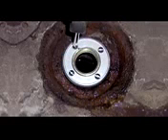Another option is to install a standpipe in the floor drain. A standpipe is an open-ended pipe that can be screwed into the basement floor drain to permit the flow of water back up as high as necessary, thereby delaying or preventing a basement flood from a backed-up sewer. Standpipes are typically 2.5 to 4 inches in diameter and can rise several feet above the floor to whatever height the homeowner thinks is necessary for protection. Because it is a pipe extending from the floor, care should be taken to make sure its presence is obvious or protected to prevent breakage or injury.